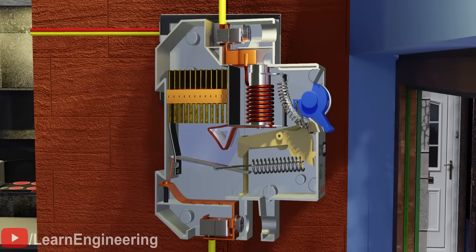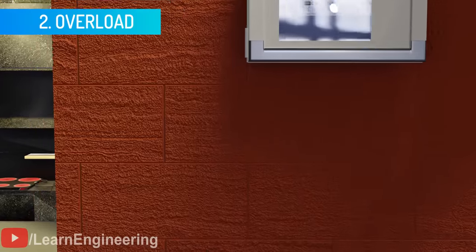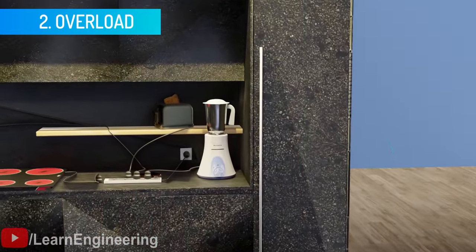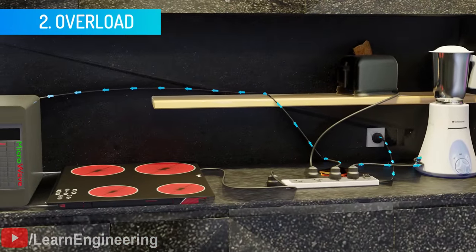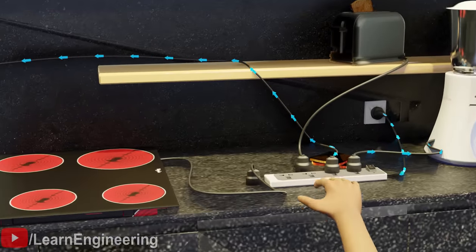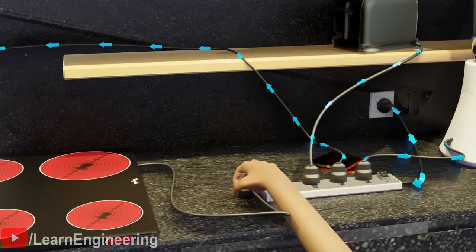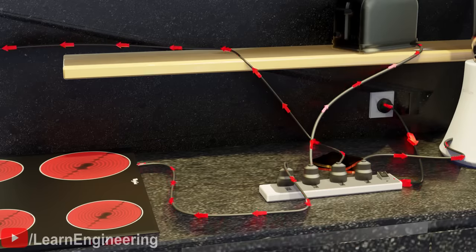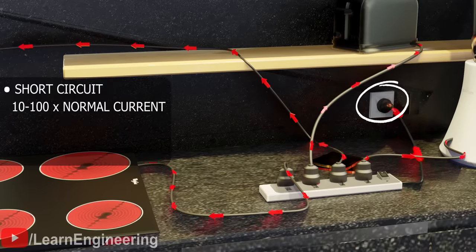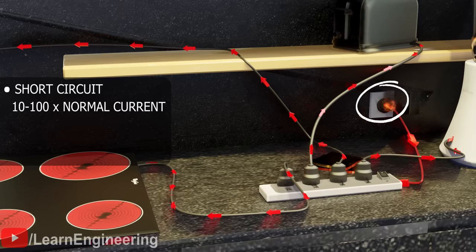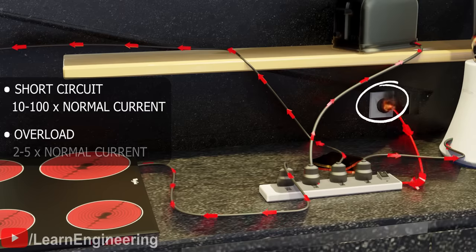Now let's see how the MCB prevents the second type of fault, an overload condition. An overload happens if you find yourself using a number of appliances at once. Since all the appliances in our houses are connected in parallel, such a scenario will lead to an increase in current. This is another dangerous scenario which we need to prevent. The current flow during a short circuit rises by 10 to 100 times the rated current, but in overload, it only rises 2 to 5 times.